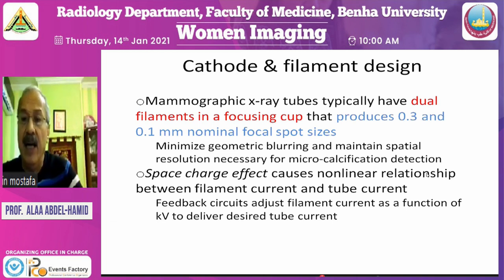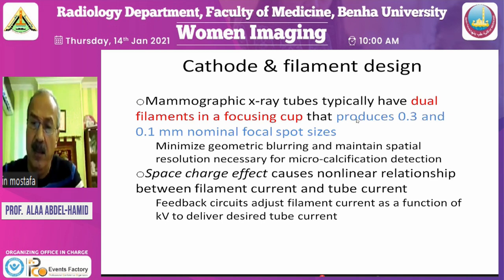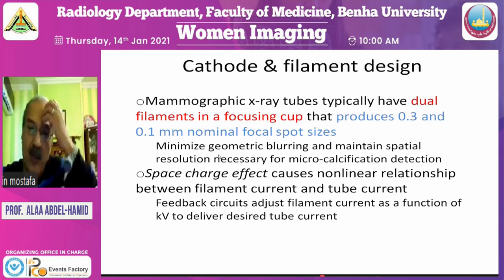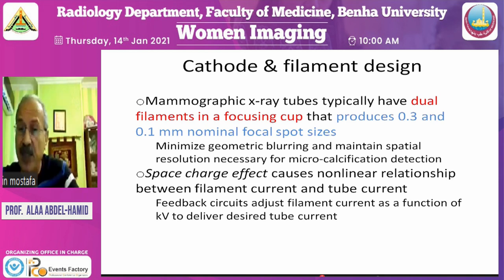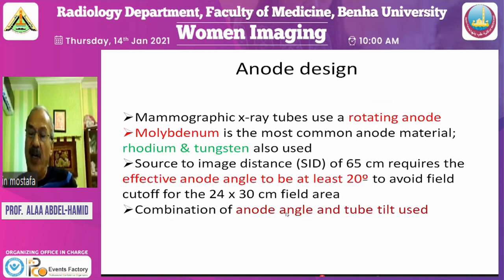Mammographic X-ray tubes typically have dual filaments. We have small focus and large focus. They are focused in a cup, and this cup produces 0.3 and 0.1 millimeter nominal focal spot sizes. It will minimize the geometric blurring and in order to get a high resolution, spatial resolutions, especially in case of micro calcification detection. Space charge effect causes a nonlinear relationship between the filament current and the tube current, and this we have here a feedback circuit between the filament current and the kilovolt to deliver desired tube current.